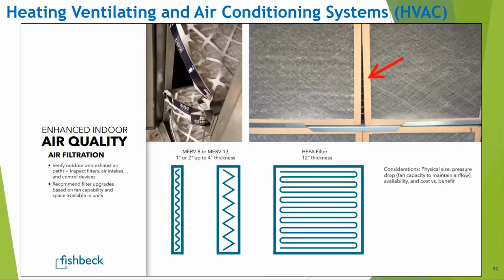Another thing that they're doing as they're commissioning our systems is looking at the filtration and where we're able to increase the filtration level of the filters that are in our systems. So for instance, you see in their graphic, MERV 8 through 9 filters range in thickness from 1 to 2 inches. And then when you get into the MERV 13s, they're often upwards of 4 inches thick. And then HEPA filters become quite a bit thicker.